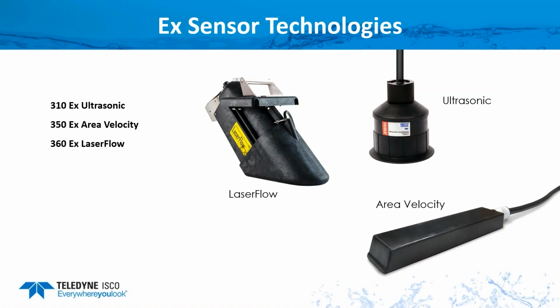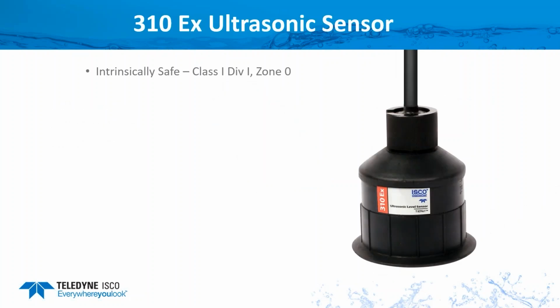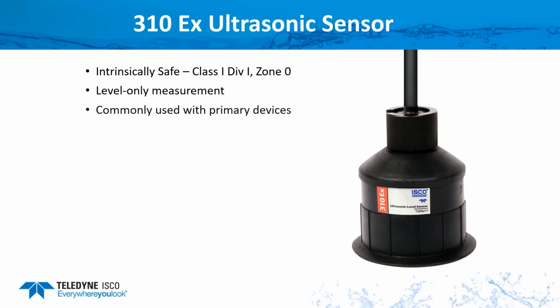Now the type of sensors that you can use, we offer the 310 ultrasonic sensor, the 350EX area velocity, and the 360EX laser flow. Now the ultrasonic sensor is rated class 1, div 1, zone 0. This is a level only measurement. It's commonly used with flumes, weirs. You can use it for overflow level measurement in your combined sewer overflows, tank level. So this is our standard sensor we've had for a long time, connects to our signature meters or the Dura tracker, and you would want to use an IS barrier to separate this from the controller.